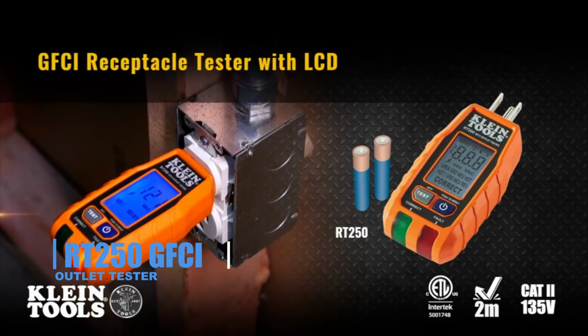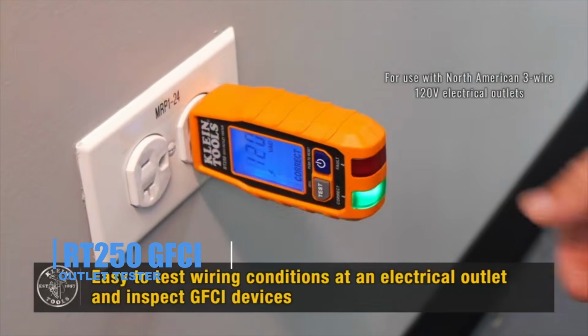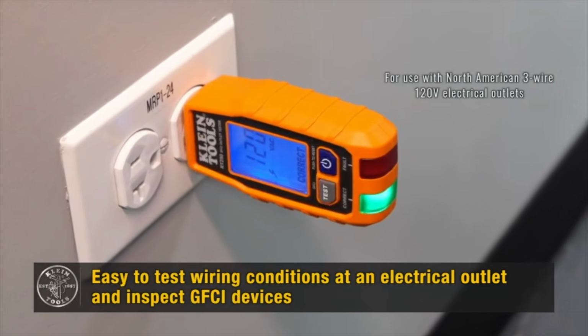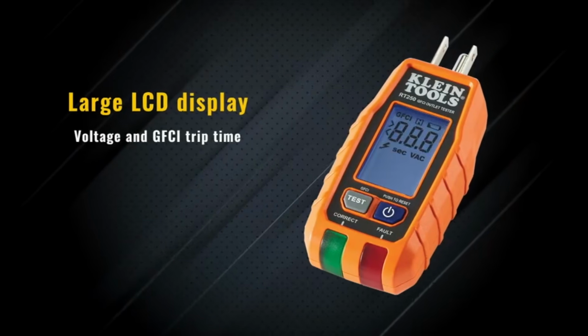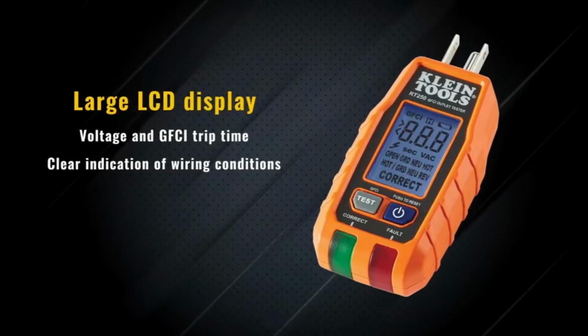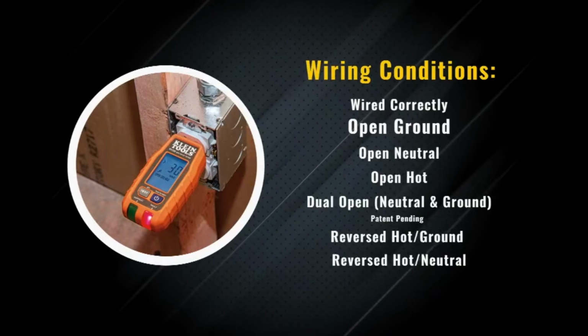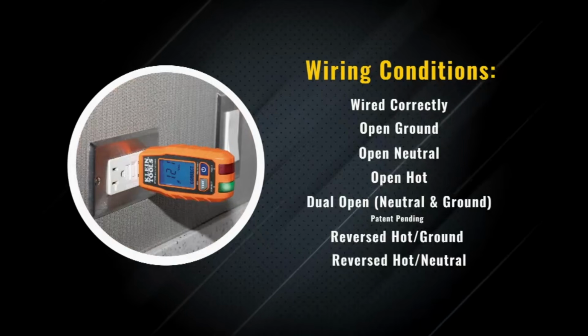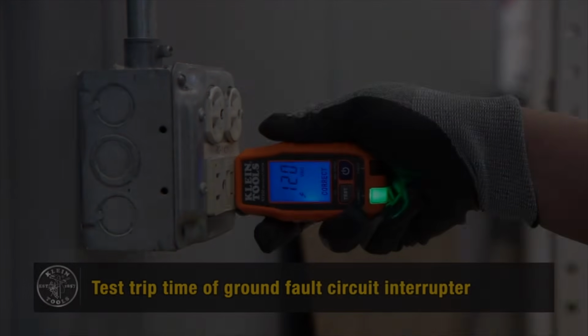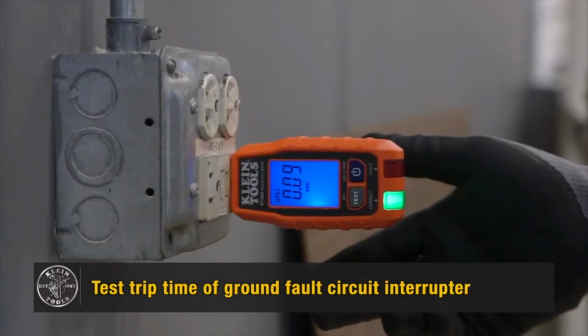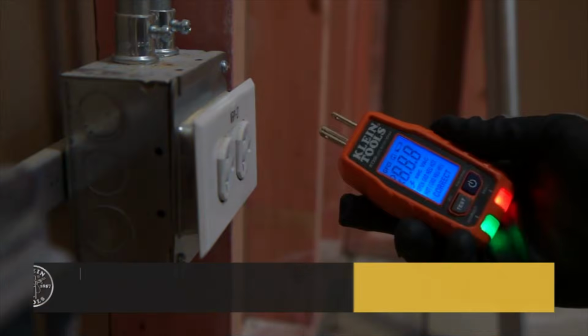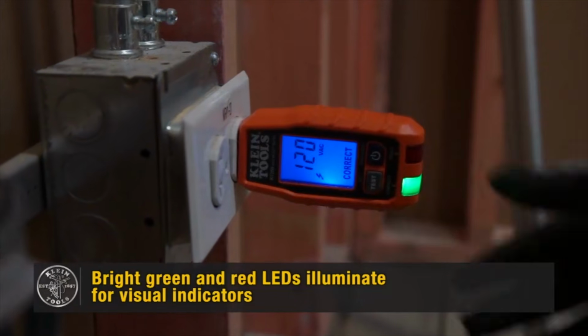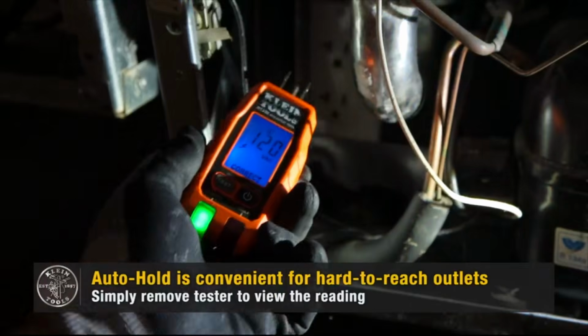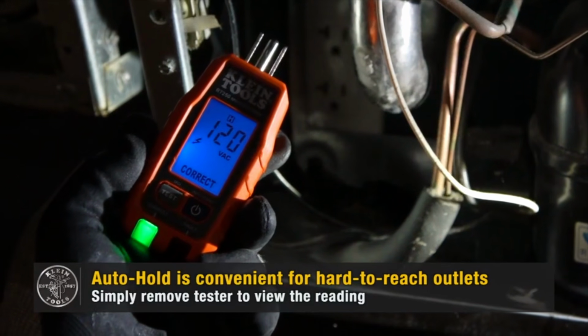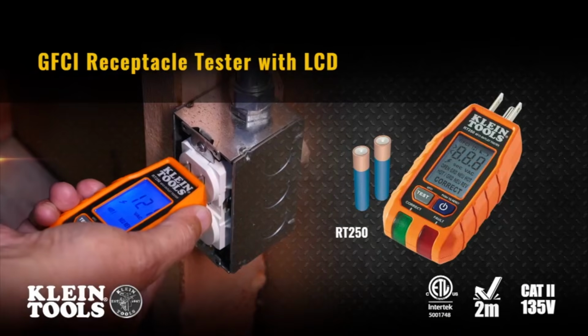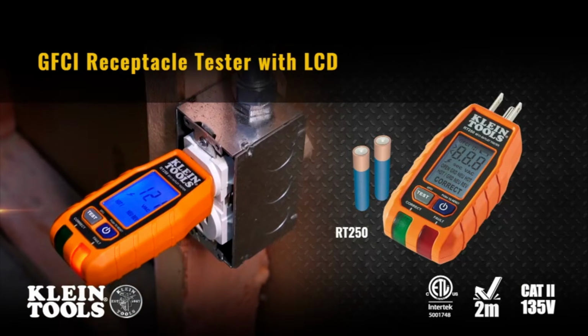RT250 GFCI Outlet Tester. When you're verifying outlet safety, especially in kitchens, bathrooms, or outdoor areas, you need a tool that gives clear and reliable results. The RT250 is designed to quickly check wiring conditions and test GFCI functionality with simple indicators. In a real-world scenario, like inspecting a newly installed outlet or troubleshooting a faulty one, this tool helps you confirm proper wiring without opening the box. It saves time and reduces uncertainty by giving instant feedback. This is a must-have tool for ensuring electrical safety and code compliance in everyday jobs.